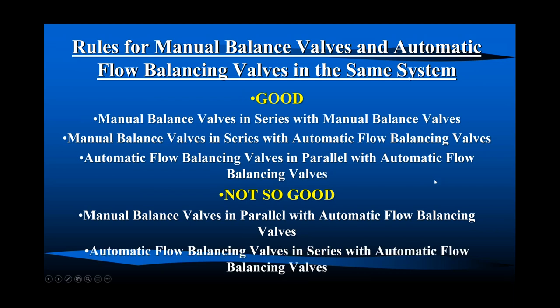So there's a question about retrofit. So really, retrofits are probably going to be manual balance valves in series with automatic. We can't put automatic valves on some terminal units and not others, because then they'd be in parallel. And we do not put automatic flow balancing valves in series with automatic flow balancing valves. You only need one flow limiter. Good.